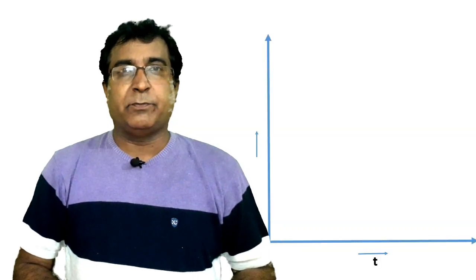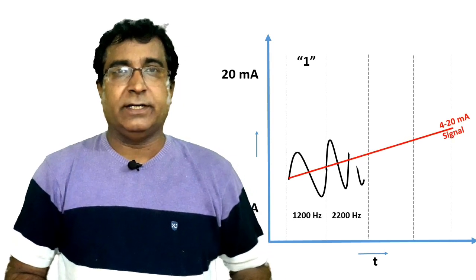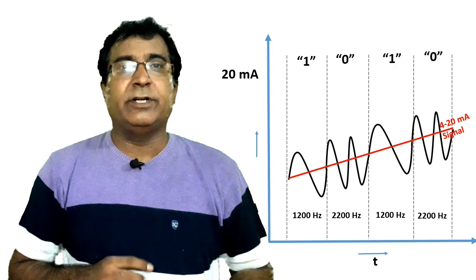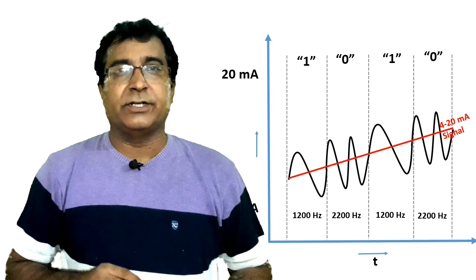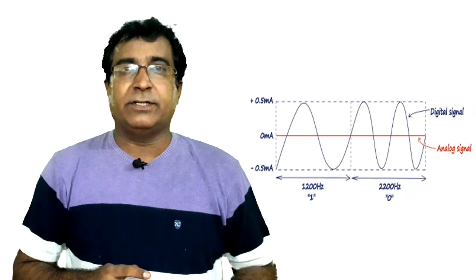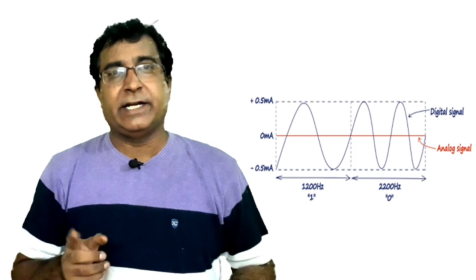Very simple. Sine waves of two frequencies are superimposed over an analog 4 to 20 mA DC signal to provide analog and digital communication simultaneously. This HART digital signal consists of two frequencies: 1200 Hz for one-bit representation and 2200 Hz for zero representation respectively. This is called Frequency Shift Keying modulation, generally termed as FSK — a kind of modulation which differs from AM and FM modulation. Since this wave basically adds 0.5 milliamps to the measured variable signal when it is in the positive cycle and subtracts 0.5 milliamps when it is in the negative cycle.